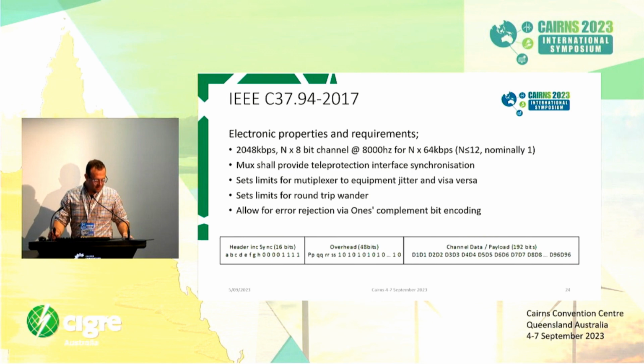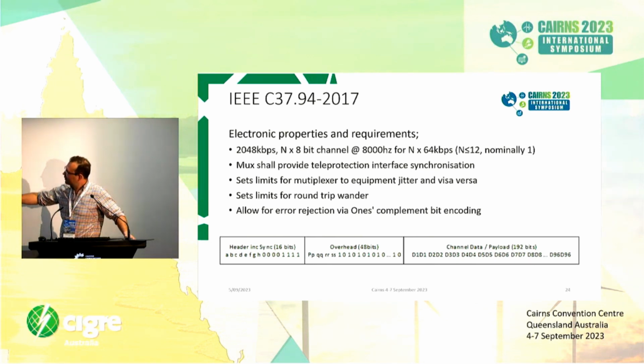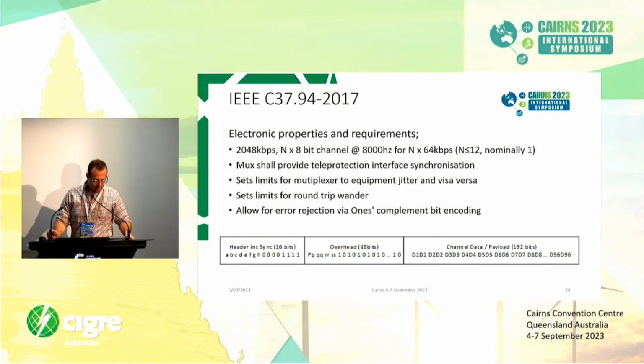So some of the important characteristics of C37.94 for later in this discussion include the synchronisation of the protection equipment: the transmit interface is synchronised to the receive from the multiplexer equipment, so the timing is provided by the multiplexer equipment. There are limitations set for local jitter, as James mentioned, and the protocol also uses one's complement for error rejection. So you can see on the slide here that for each data bit there are 2 positions to be filled, that's 1 and its complement, for encoding on the wire.